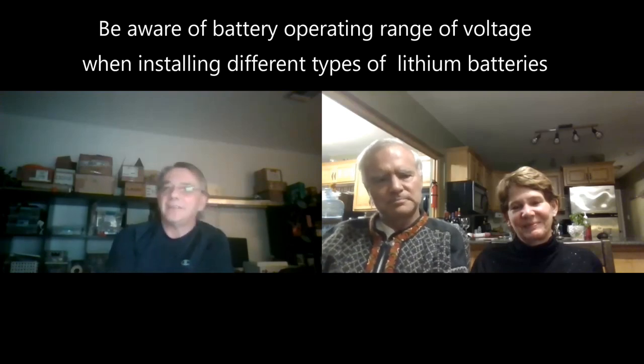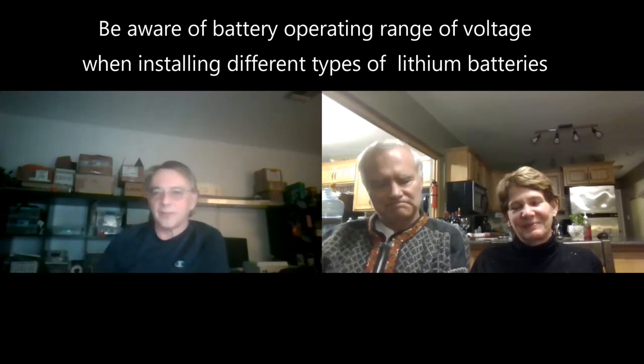So explain that in more detail, because this is super interesting. Why is too low a voltage a problem? The rest of the system isn't designed for it. When we say the system has a nominal voltage of 24 volts, at full voltage the batteries are almost at 27 volts, 26.8 depending, and the minimum voltage is 21 volts. The Tesla pack, the way it's designed, has a maximum voltage of 24 volts and a minimum of 18. So as soon as you're below 21 volts, half your equipment stops working because it's below the normal operating range — the battery isn't empty.